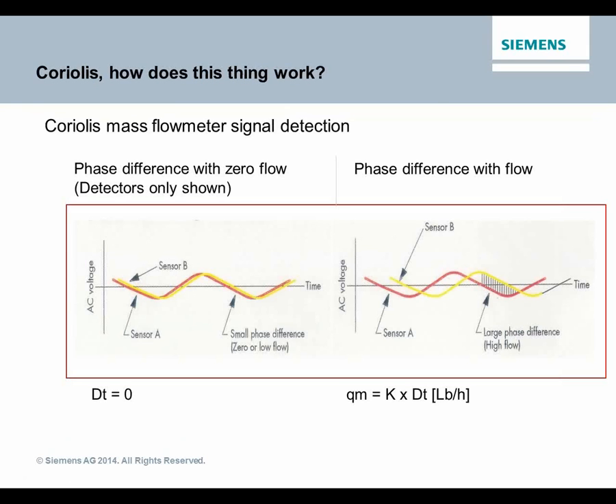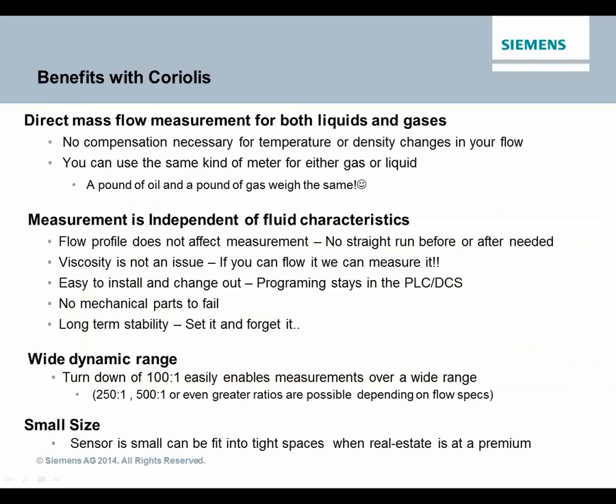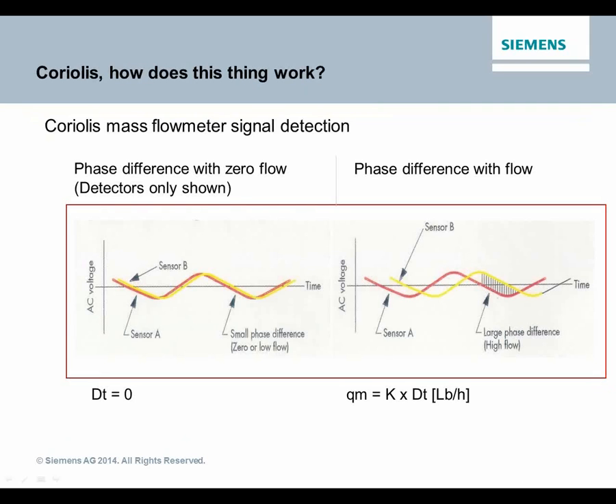So we've now taken 6 minutes of our 30 minutes or more, I don't have a clock here, going over this. Now, this slide pretty much dictates what it is that is at the heart of Coriolis, in that on this side we have no flow. I have no pointer here. So on this side, we have flow. We have a tube vibrating, but A and B are the same, right on top of each other, so there's no flow rate. As soon as you get a flow, A and B are out of phase, and it is the phase difference that we're measuring.